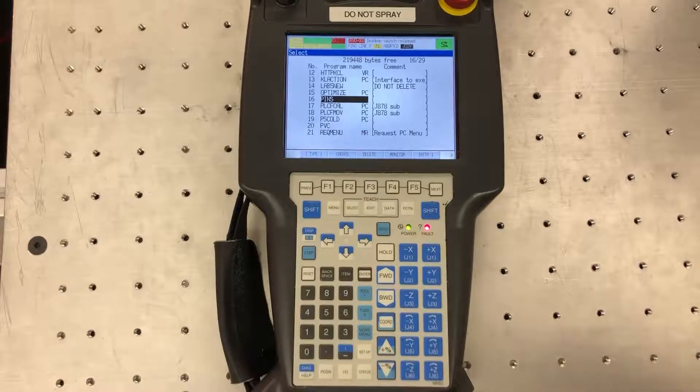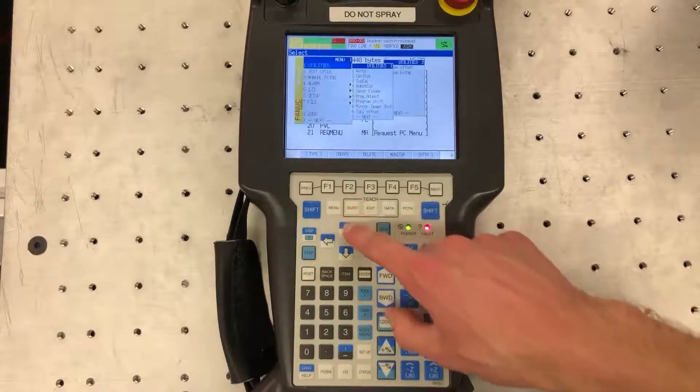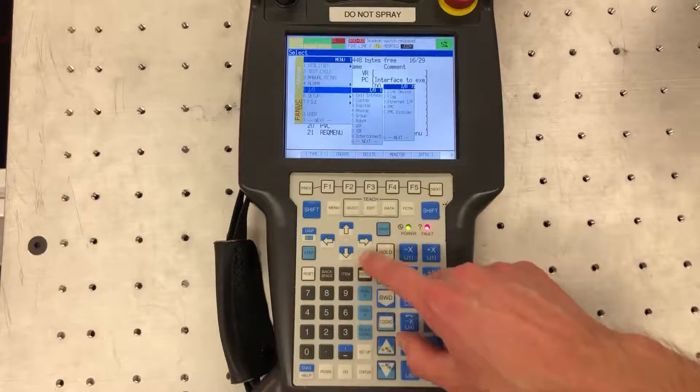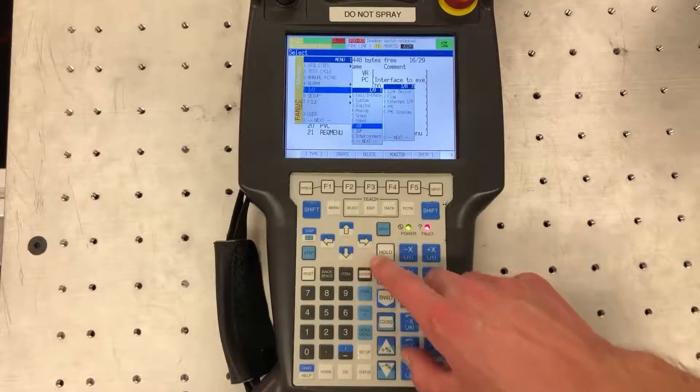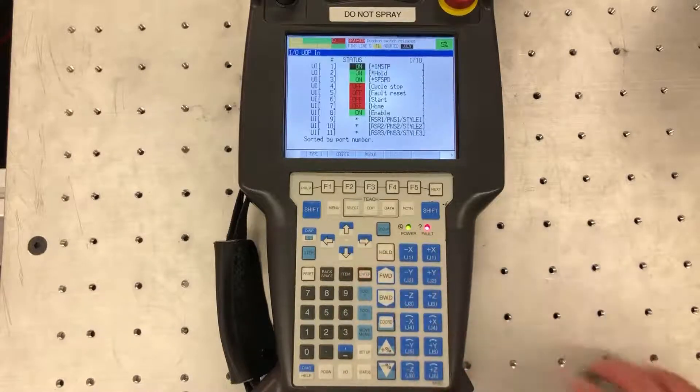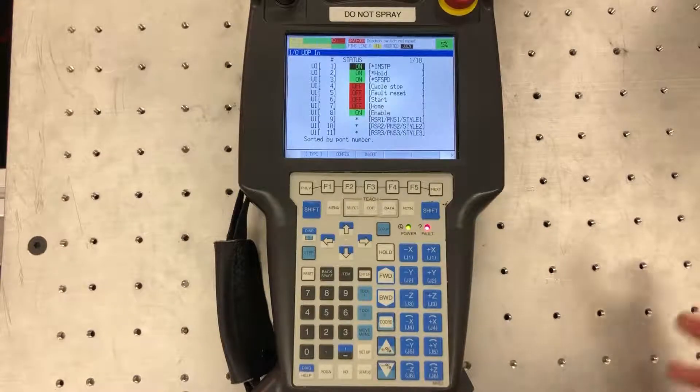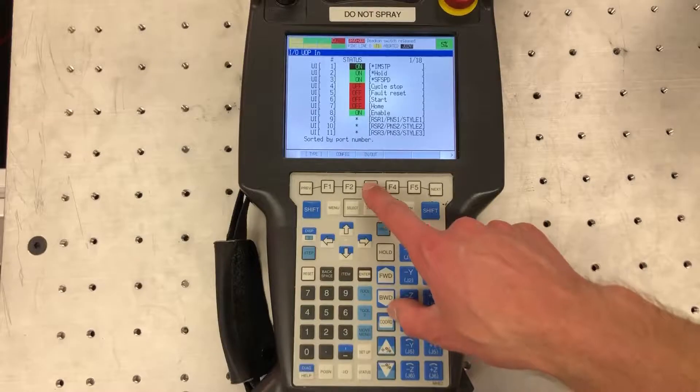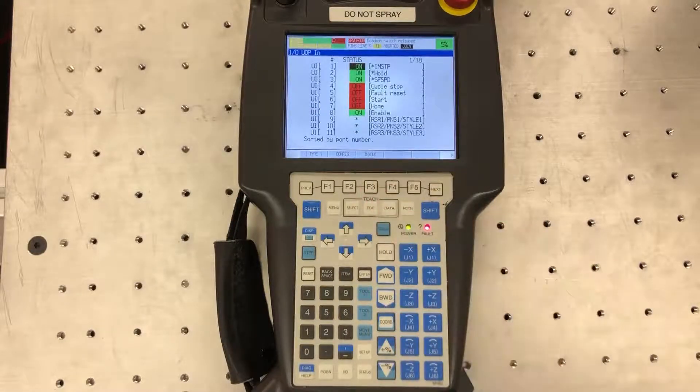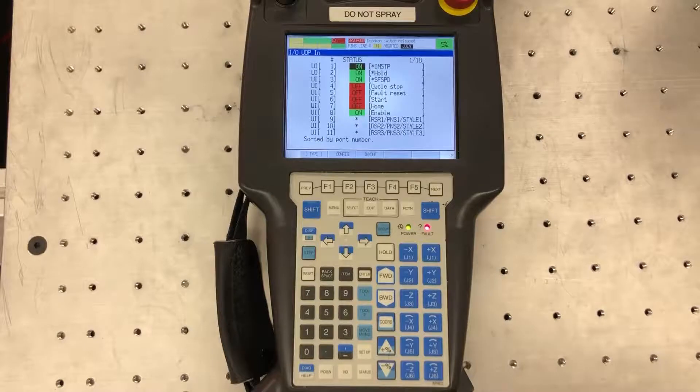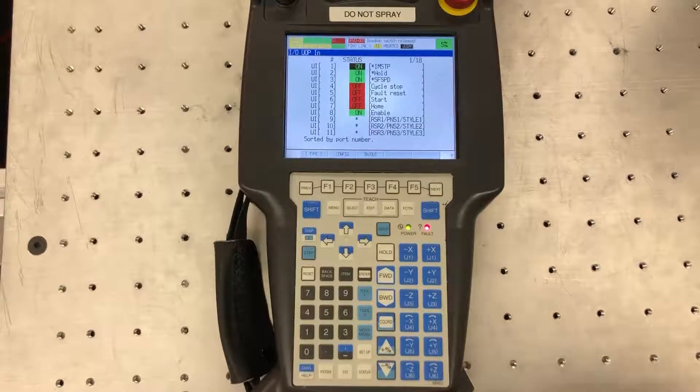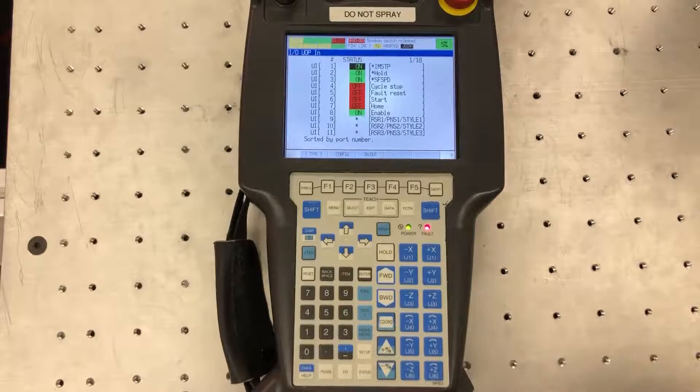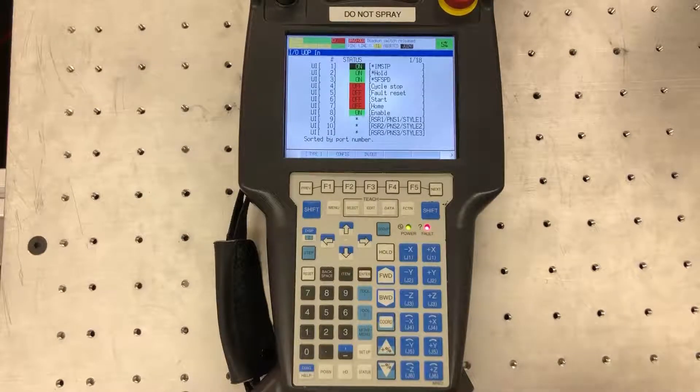First, we're going to go to menu and scroll down to I/O. You're going to find UOP, hit enter. It's going to default to show you either whether it's the UOP inputs or outputs, but you can just toggle between those using F3 outputs or inputs. Most of the time you're really only going to need the first eight bits in these UOP menus and that's what I'm going to show here.